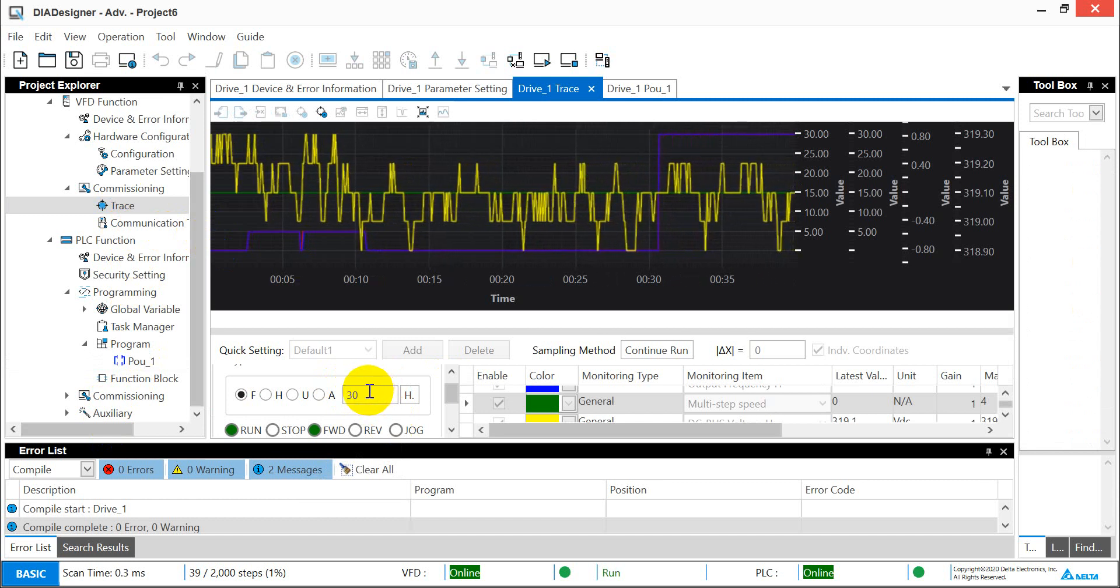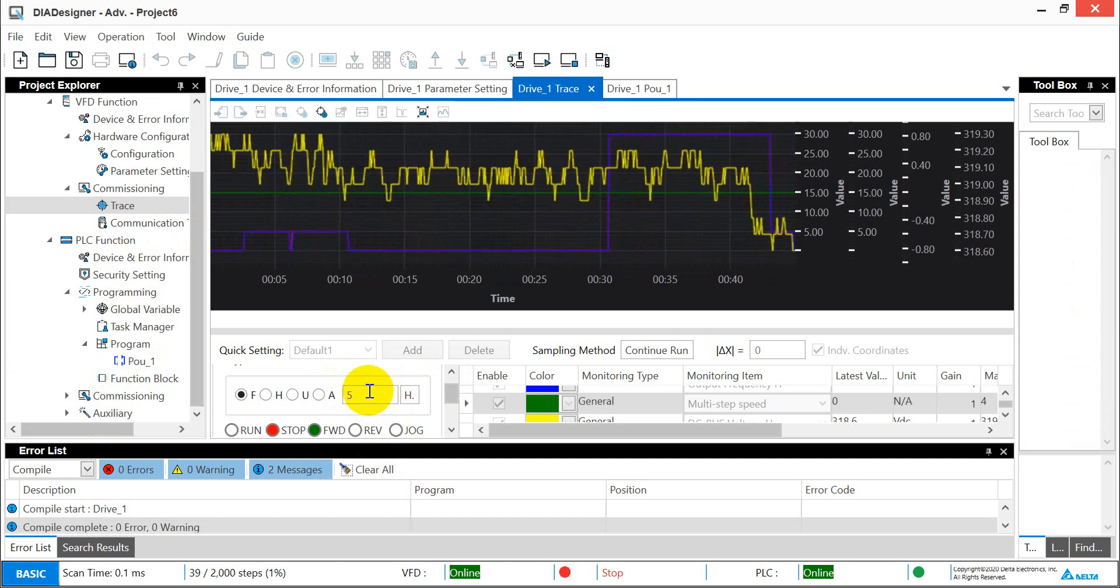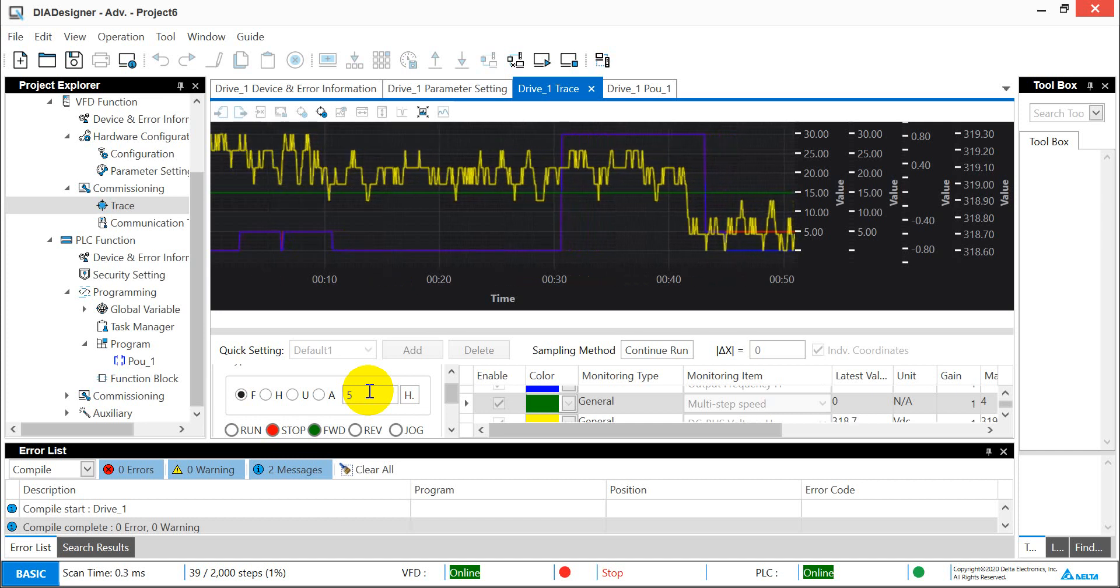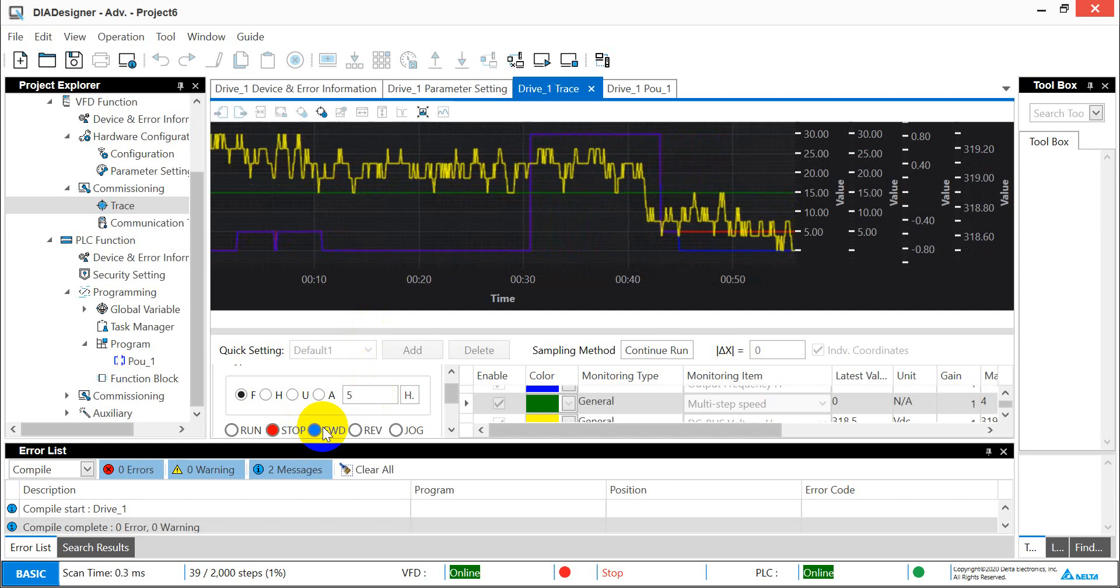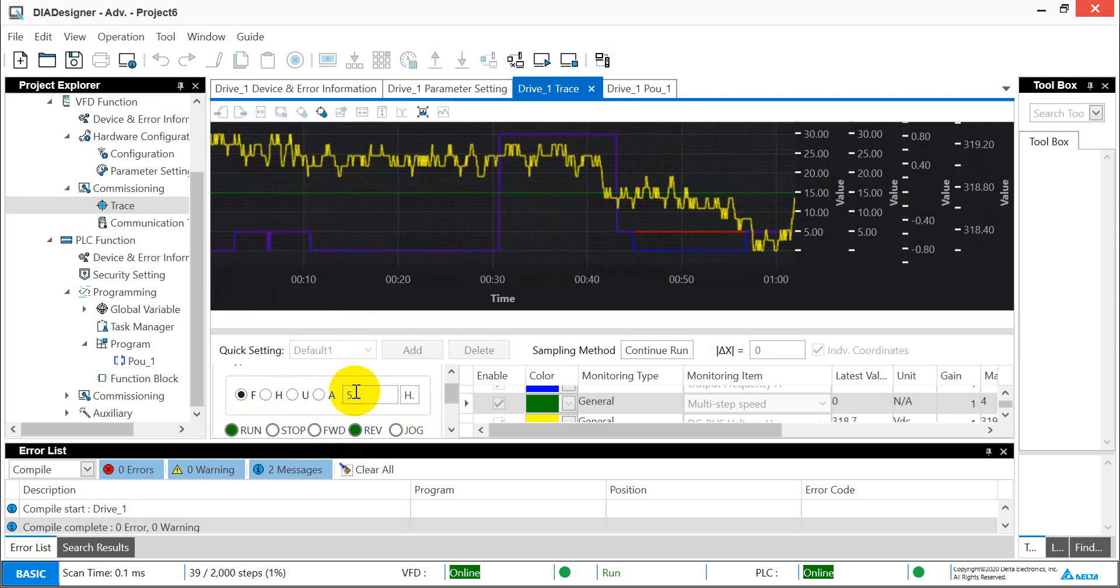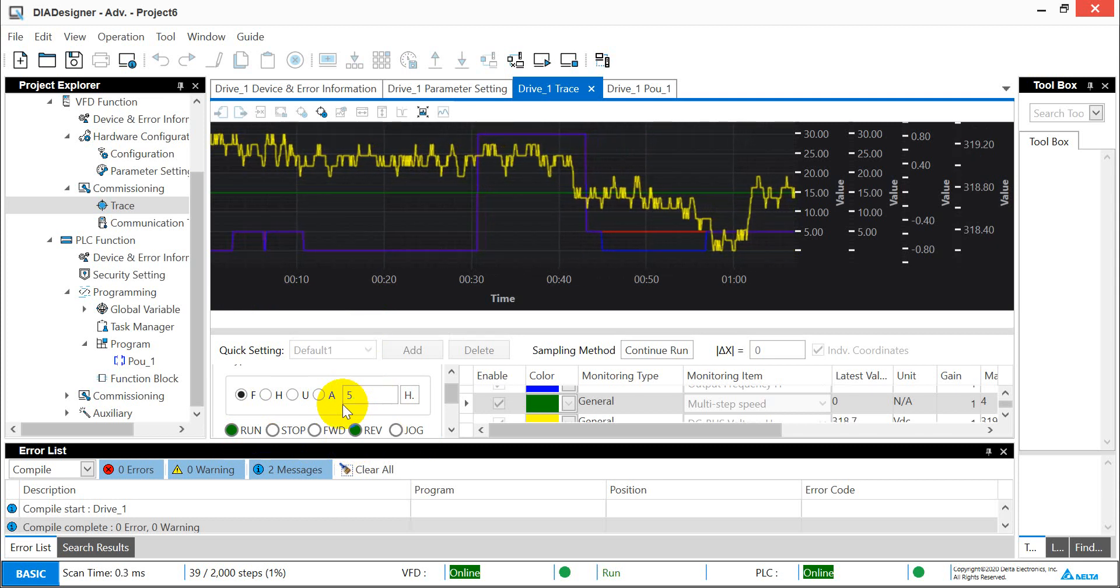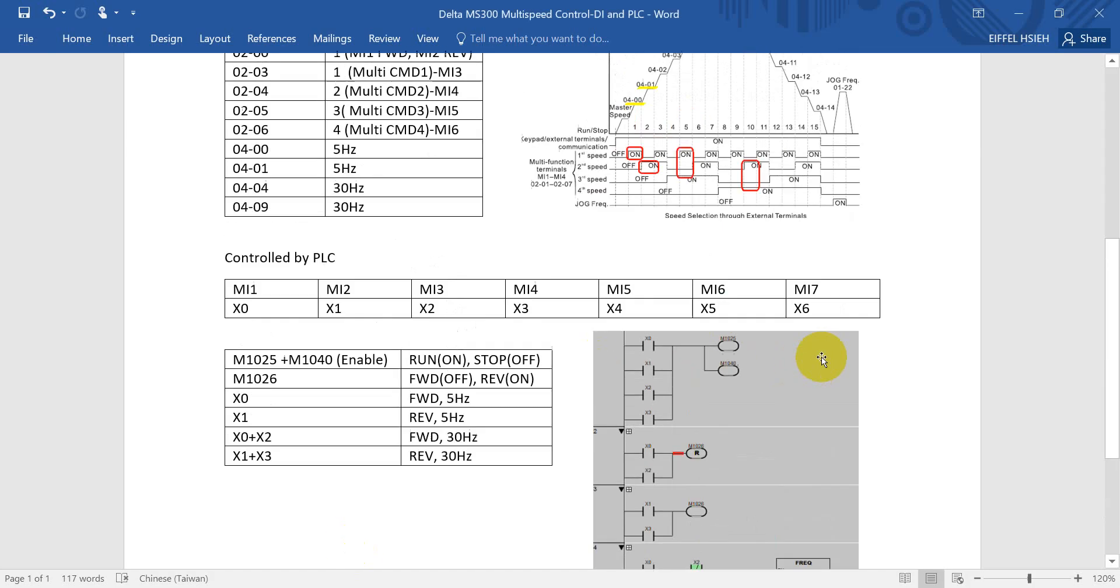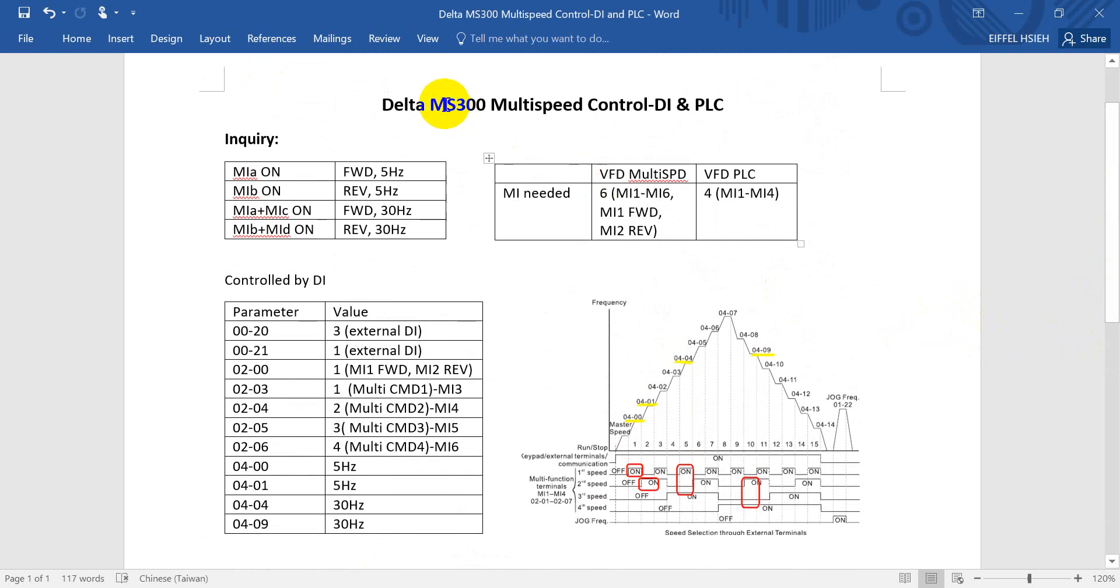Next we will remove the MI1 and MI3, so you will see now it becomes stopped, but you can see now keeping the forward. Now we give the signal to MI2, so you can see it becomes run status, reverse, 5 Hertz. Then we give the signal MI4, so you can see now it switches to 30 Hertz. So this is the two methods how to achieve this inquiry for MS300, either by PLC or digital input. Hope this one can help, thank you.